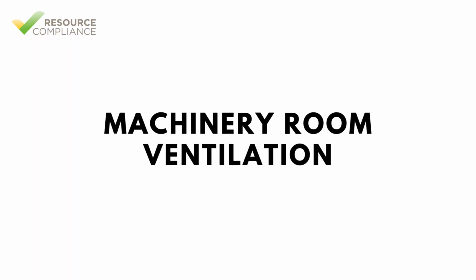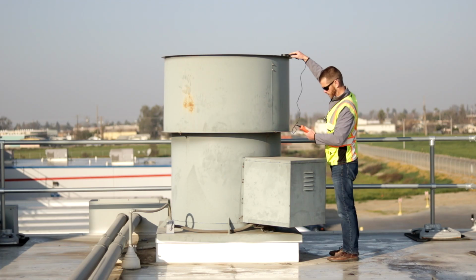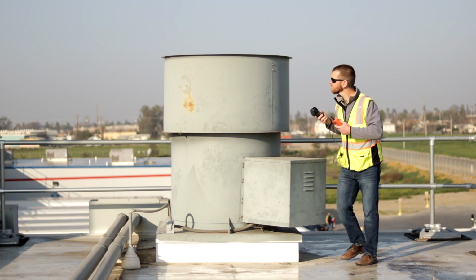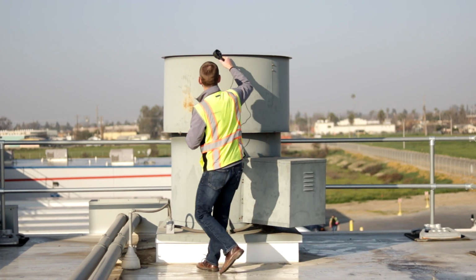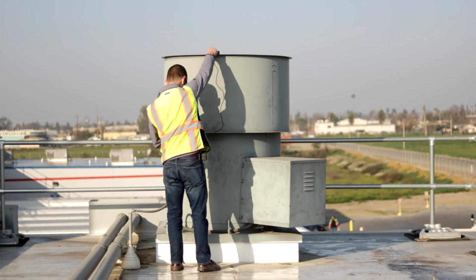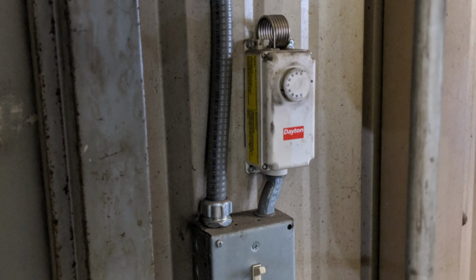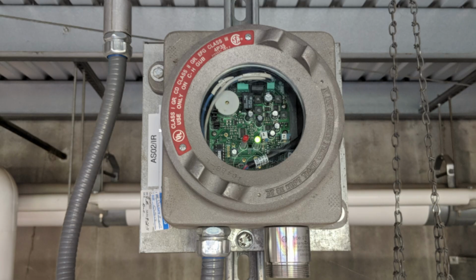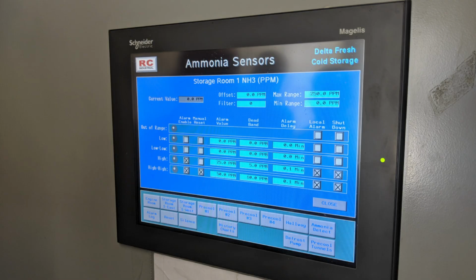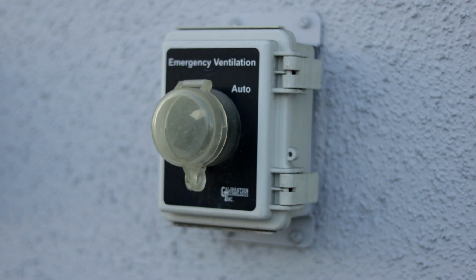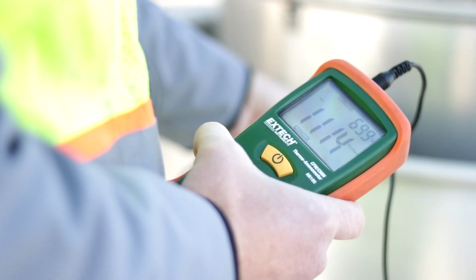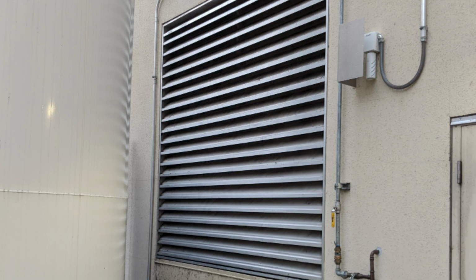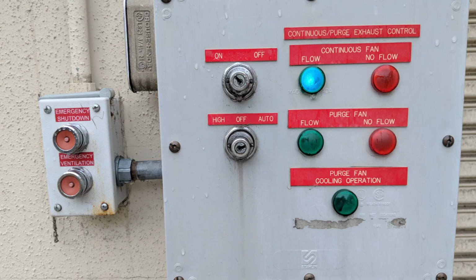Machinery room ventilation systems should be inspected routinely to ensure the ventilation system is operating as designed. Annually, the system should be functionally tested to ensure temperature-controlled ventilation is working and emergency ventilation is activated at the proper gas concentration. For ammonia, this is typically 150 ppm. The emergency ventilation switch works, the ventilation fans provide adequate airflow, intake louvers are functioning as designed, and all audible and visual alarms are working.